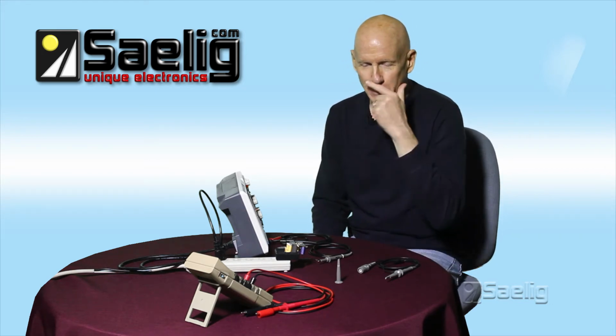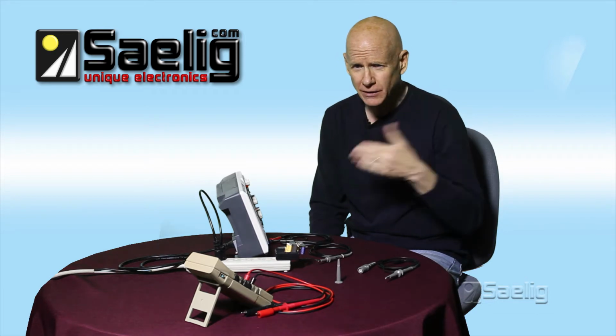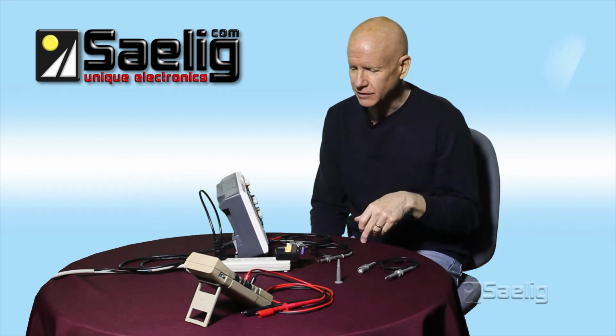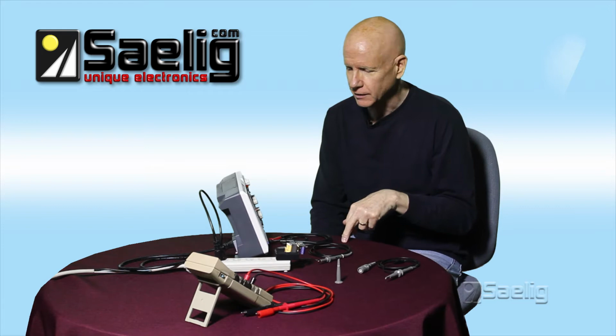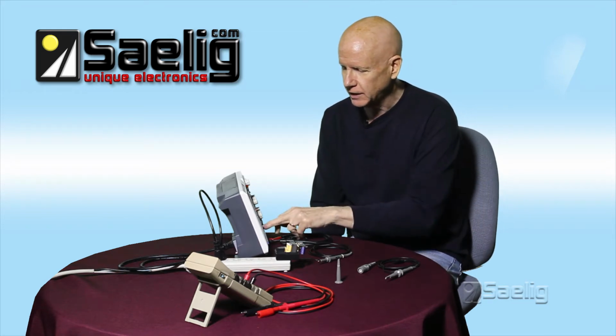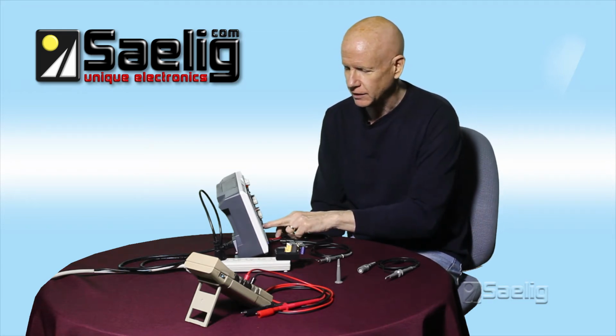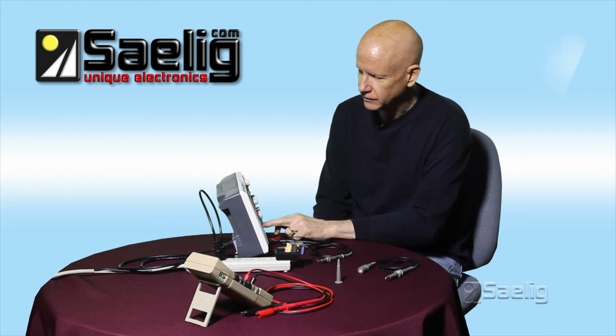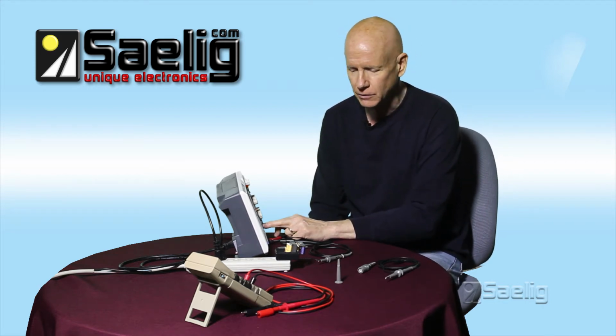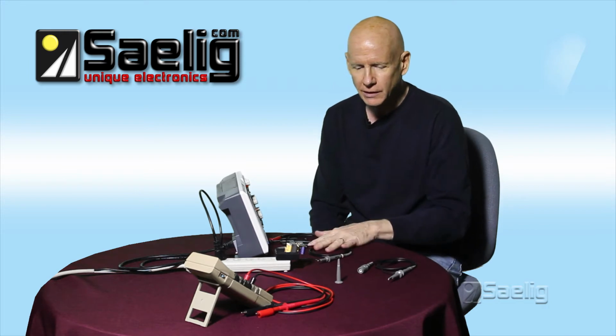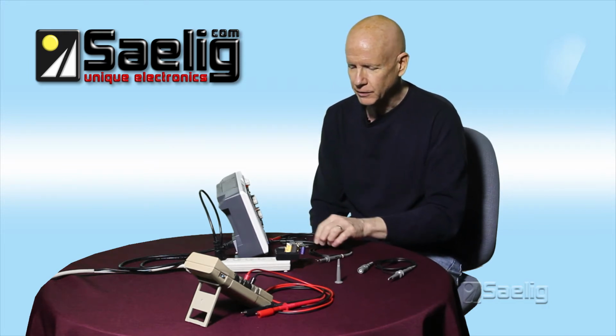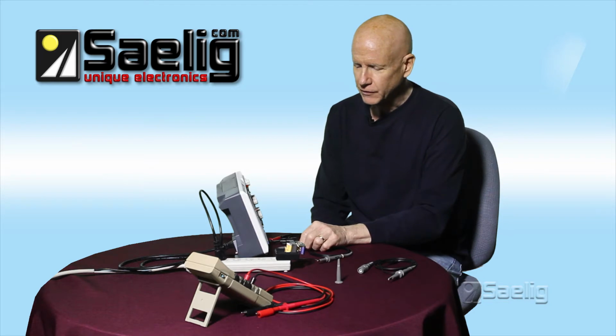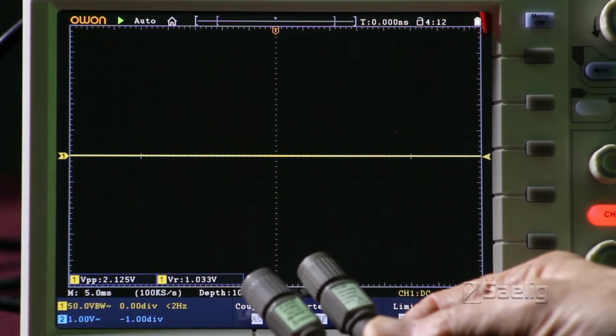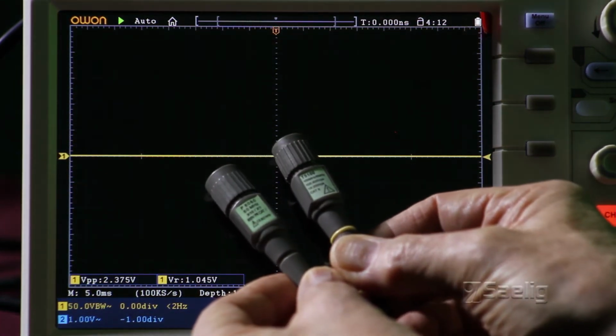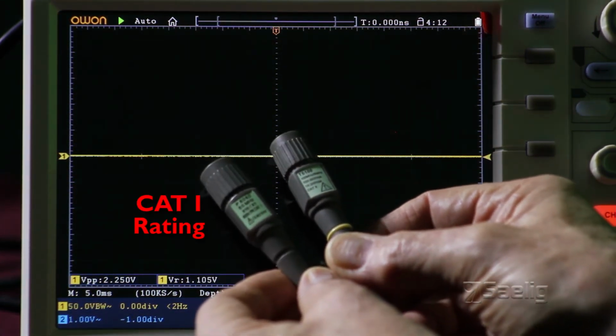One of the things that I'm going to be mentioning from time to time from here on out through the rest of these sessions is the CAT ratings on some of our products. The scopes usually have an indication as to what category they're rated for. For instance, this scope here says it's rated for Cat 2. The probes are also rated, and it's important to look at them because, for instance, these two probes look very much alike. They're slightly different model numbers. One of them, the one on the left here, is rated for Cat 1.